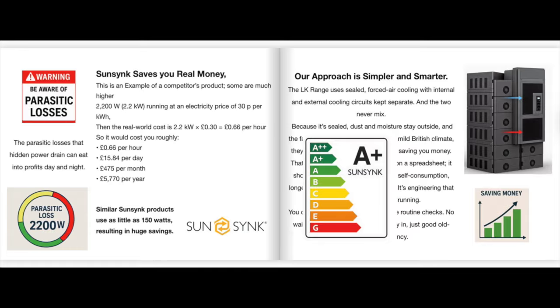If you choose high density batteries and need cooling systems running 24/7, think about how much energy that system is drawing. Whereas in a moderate climate like the UK, a lot of the time you don't even need to run any cooling system. Using an air-cooled, super low density battery system, maybe 90-99% of the time depending on the weather, it's not running at all, and you're not wasting that immense amount of energy.